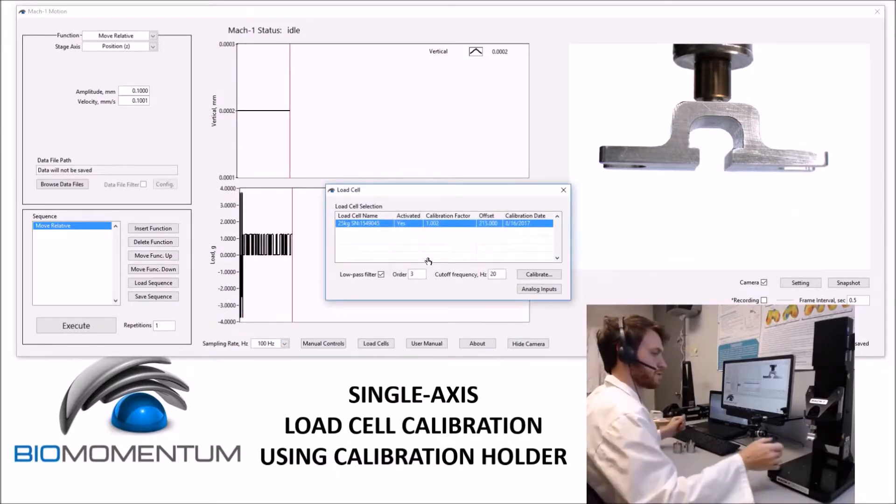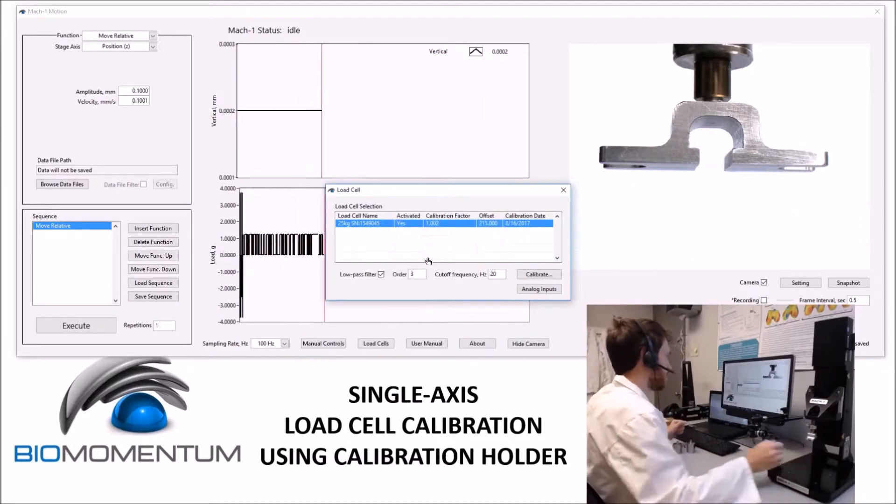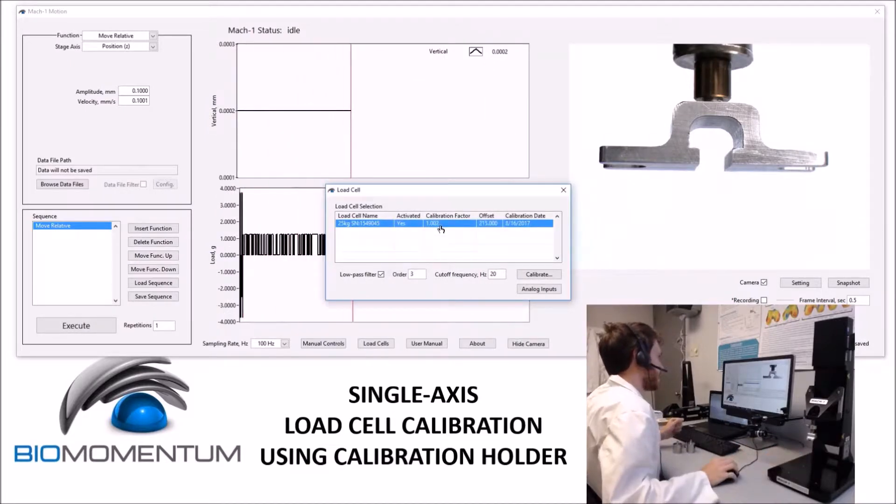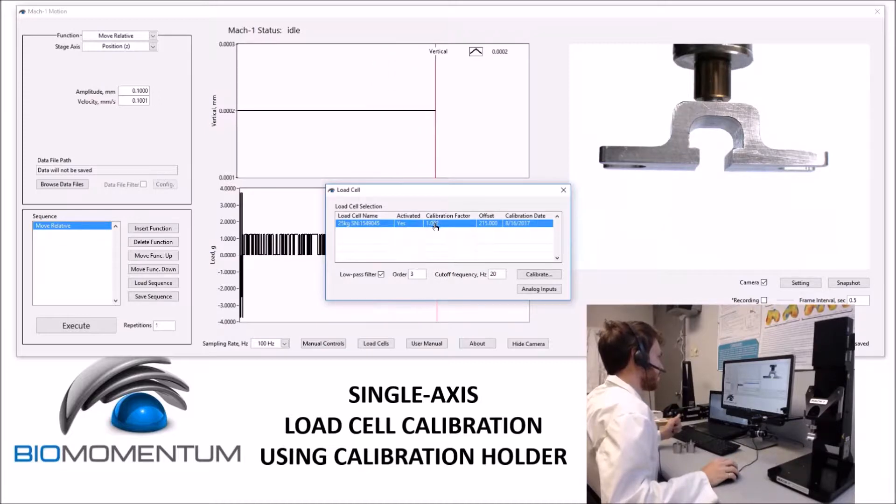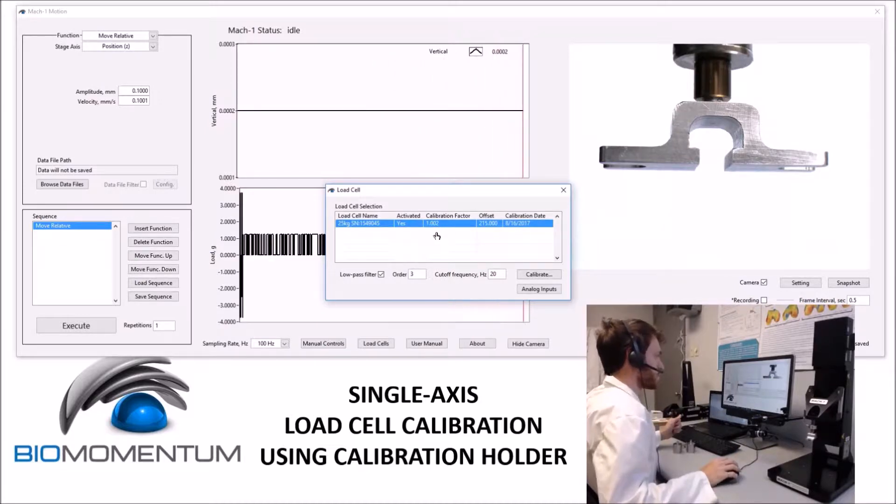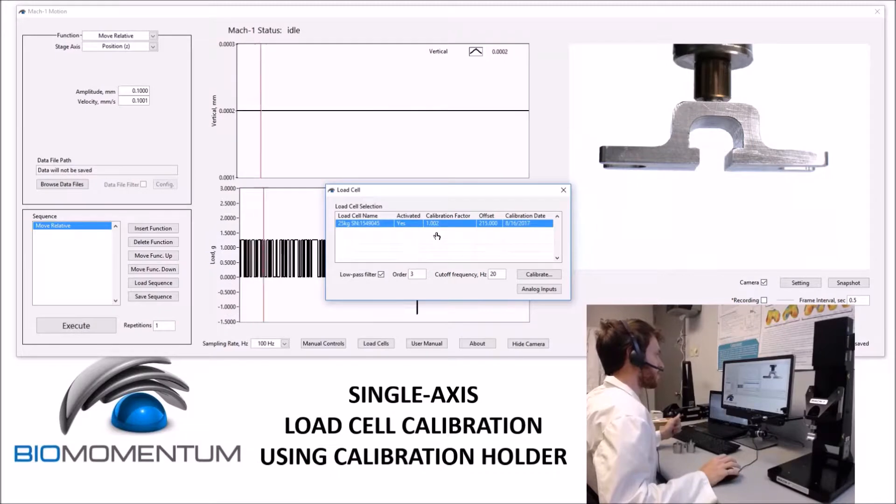The load cell is now calibrated, and the calibration factor is always supposed to be within 5% of 1.00, so between 0.95 and 1.05.